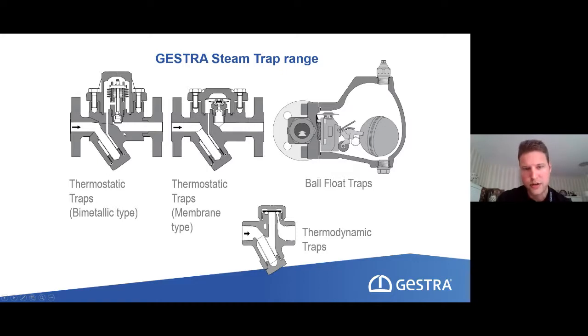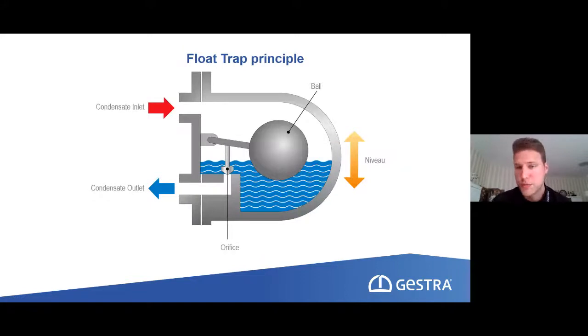But then the other ones go into operation. All right, so the principle of a ball float steam trap, which is the first one we are taking a look at, is rather simple. So we have a condensate inlet, we have a ball float, and we have a condensate outlet. And the water level, which will increase by appearing condensate, will sooner or later lead to a lift of the plug. And the plug is lifted then, and the orifice is open, so the condensate can be discharged.